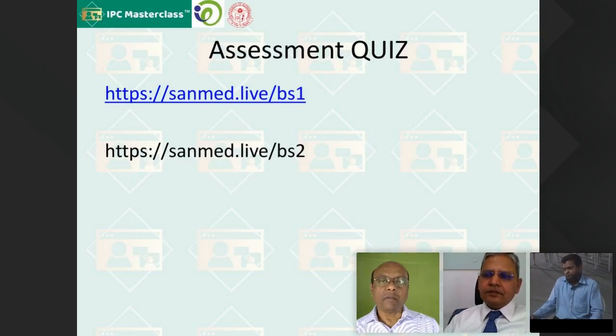The next question we have is on the biosafety cabinet. Dr. Deepa is asking what air velocity, filter integrity, and particle count are required for calibration of a biosafety cabinet. The biosafety cabinet requirements differ across biosafety levels 2, 3, and 4. An air velocity of 0.58 meters per second is maintained in biosafety level 2. In biosafety level type 2B, the same velocity is there, but it is supplemented with a negative pressure inside. For the particulate air count, there is a different formula to calculate it, and there are different standards.